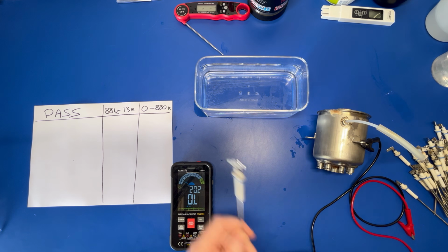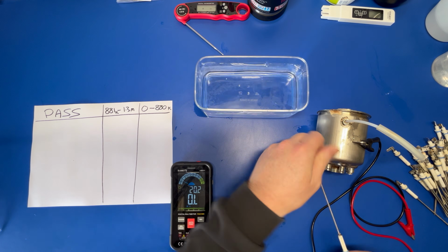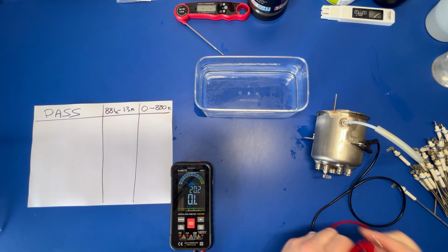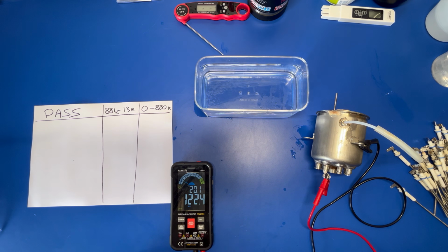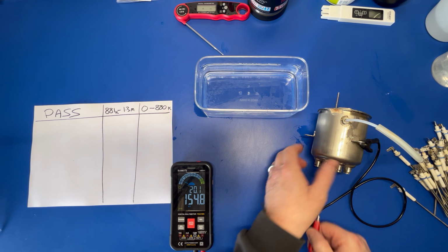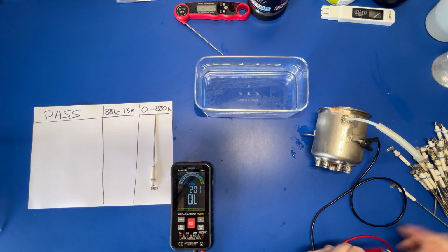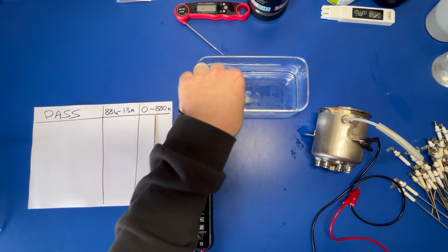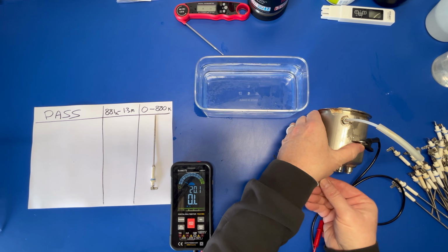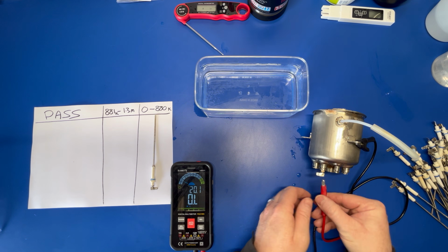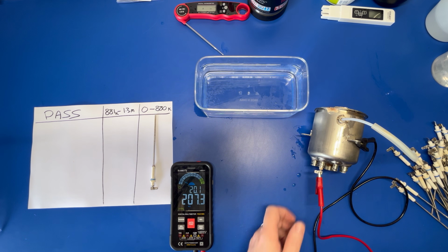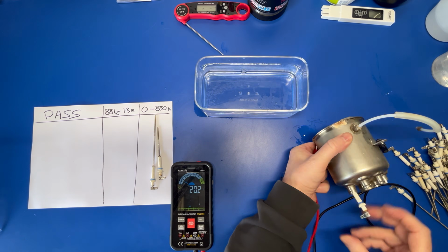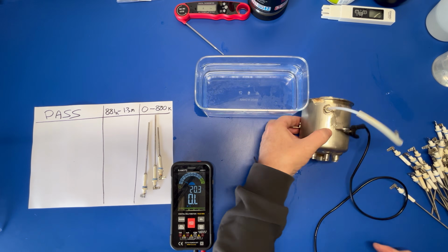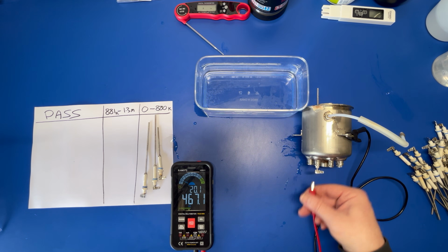What I'm doing here is wetting the probes in just plain tap water, then inserting them into a boiler and measuring the resistance. This is to replicate them being inside a boiler full of steam. I'm wetting the tops too to simulate probes that may also be leaking. Hopefully this covers all cases. I have a piece of paper dividing those that would certainly fail a descale and those that would pass or scrape by, as is the case for many of these.